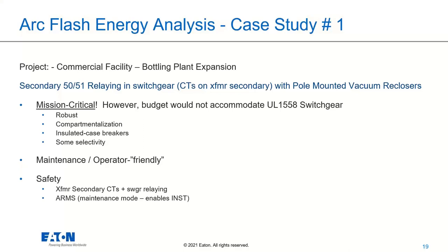And I'll describe what that means in more detail. But really, when you have certain relaying or protection, you might be familiar with things like maintenance mode or hotline tag out. There are ways you can manually intervene and tweak settings while you're working on equipment, and that can make it quite a bit safer. However, that does require human intervention. That requires someone to go and activate a switch or a signal in that piece of equipment and turn that on. That's effective, but what would be even better is something that is always protecting, constantly looking and constantly able to react with a level of speed that's going to keep that arc energy low.